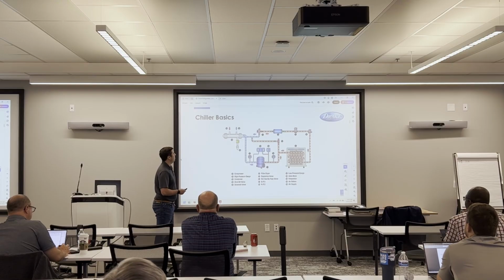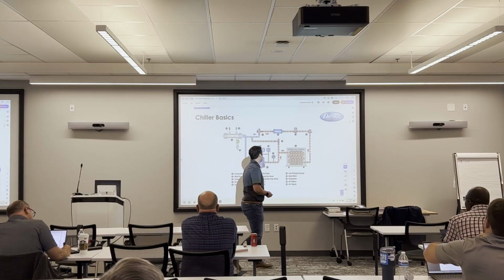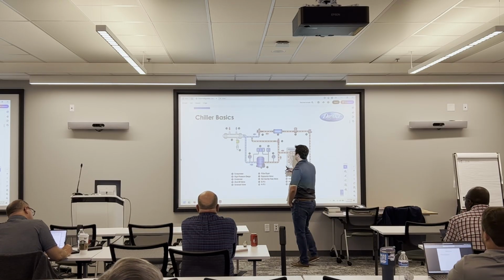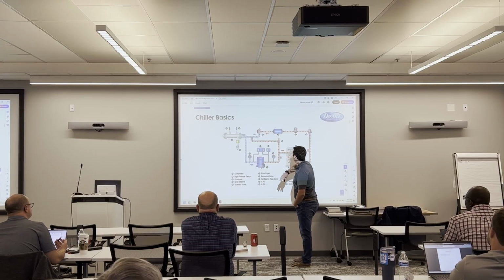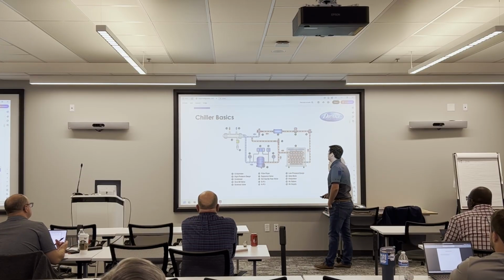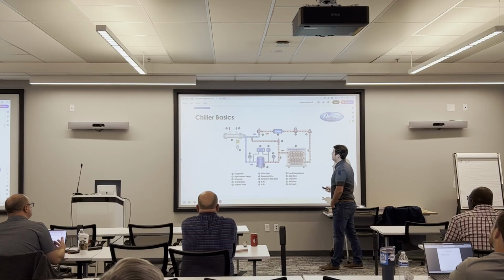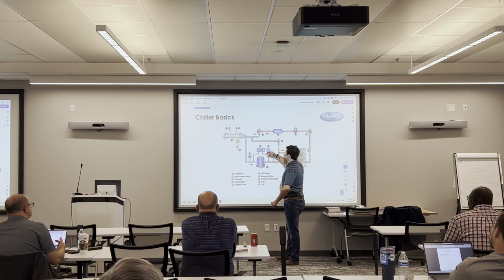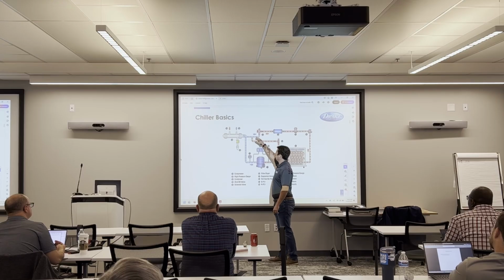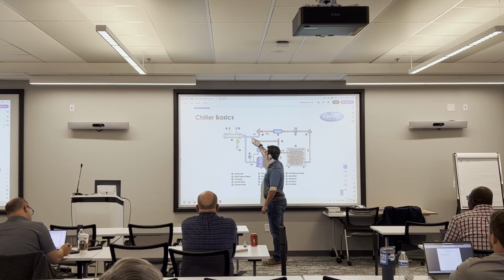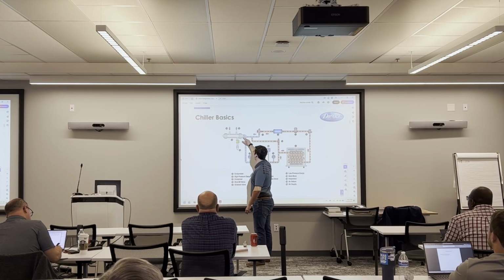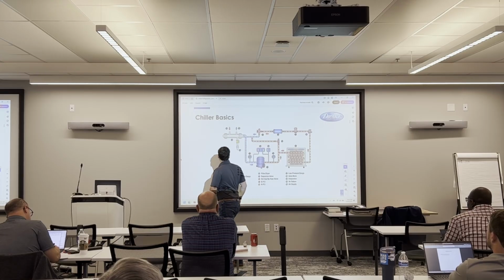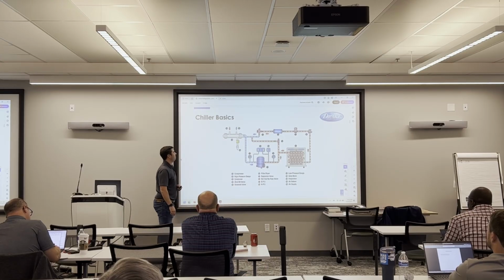So what's going on in the refrigeration circuit? There's a couple of things to note here. Everything in blue represents low pressure, low temperatures, and everything in red represents high pressure, high temperatures. You can see we're coming into the evaporator as a liquid vapor mix, a low pressure, low temperature liquid vapor refrigerant. As it leaves our evaporator, that refrigerant's going to boil off from absorbing heat from the water or glycol circuit, into a full gas. We'll call that superheat.